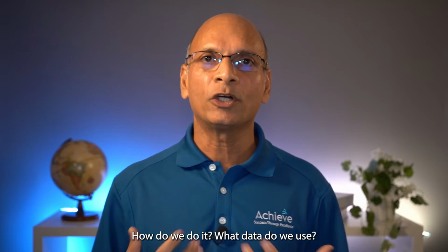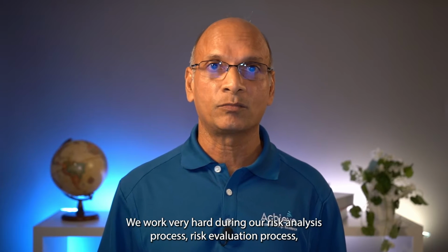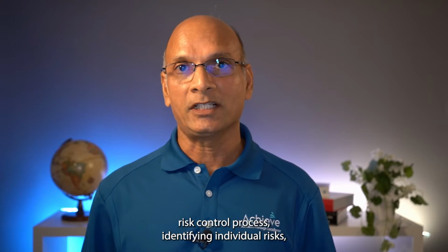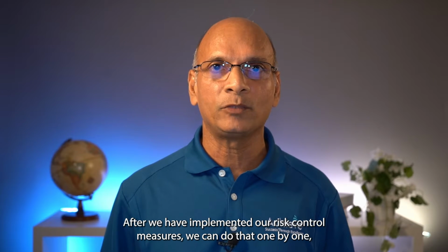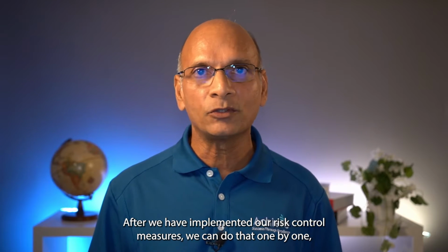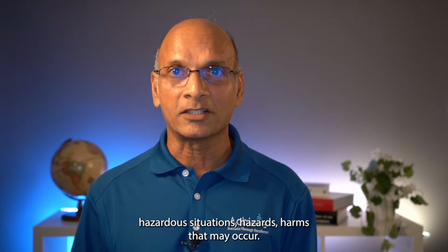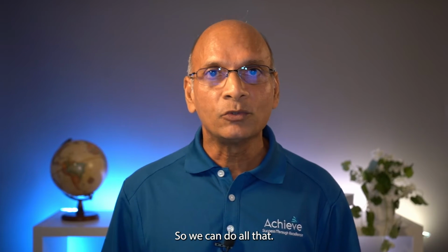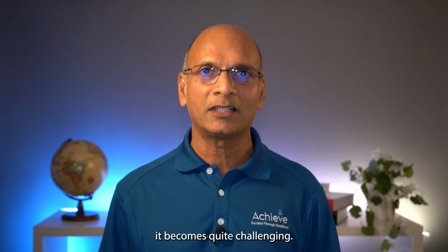How do we do it? What data do we use? We work very hard during our risk analysis process, risk evaluation process, risk control process, identifying individual risks and then evaluating those individual residual risks after we have implemented our risk control measures. We can do that one by one, having identified all the sequences of events, hazardous situations, hazards, harms that may occur. So we can do all that. But when it comes to the overall residual risk evaluation, it becomes quite challenging.